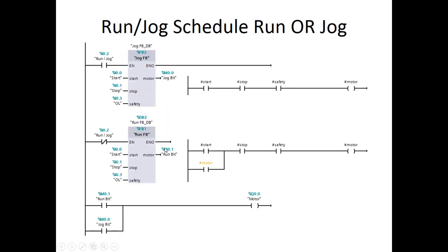What we did differently is we wrote subroutines using local tags. Here's the example of a local tag going into this subroutine, and here's the example of a local tag going into this subroutine. Now remember, I have a start here and a start here, but because these are local tags, this subroutine doesn't understand what this subroutine is doing at all. These are two different tags — if this one's true that doesn't mean this one is true.